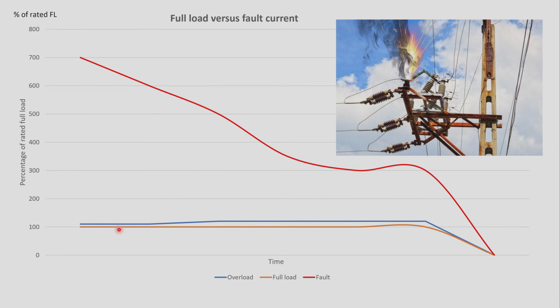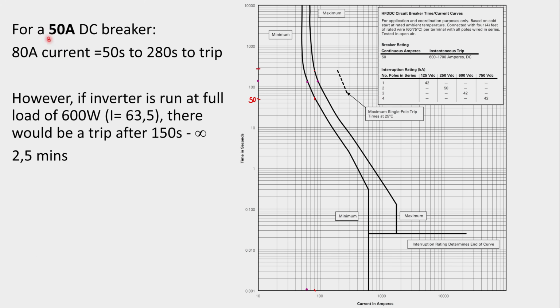So let's look at a practical example. Okay, let's say, for example, I chose a 50 amp circuit breaker. Notice that a 50 amp circuit breaker is considerably lower than that 80 amp overload current. Now, let's look at where 80 amps sits on this graph. So there's 10 amps, 20, 30, 40, 50, 60, 70. Okay, so this red dot here is 80 amps. So if I extend the line, I'm there.